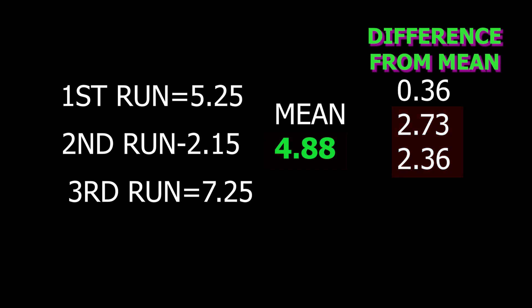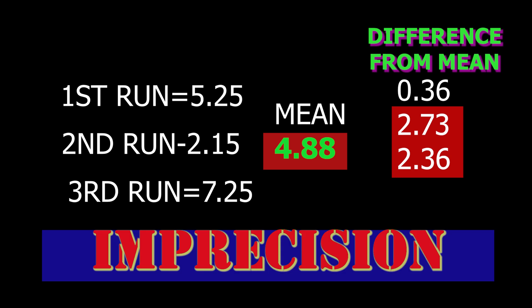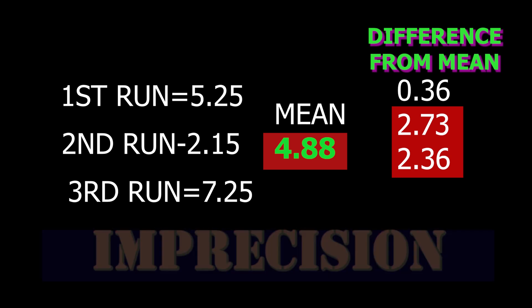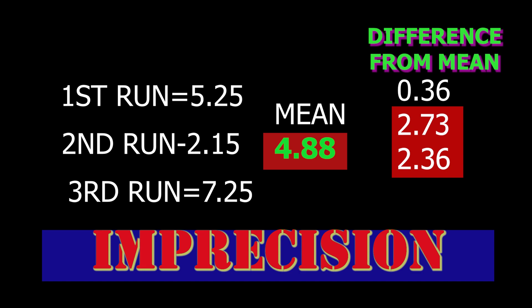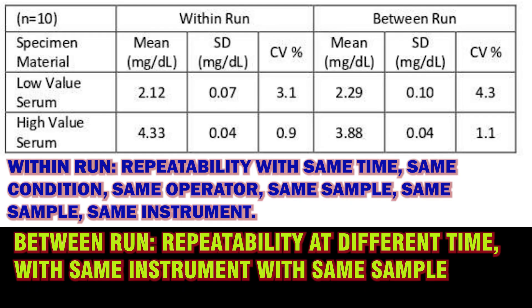If the instrument has very bad precision, the readings are far away from each other and the instrument cannot reproduce the same value, which indicates the instrument needs to be fixed before recalibrating the analyte. When we program the analyte calibration parameters, the instrument is programmed with a coefficient of variation percentage — the maximum percentage of variation allowed to pass calibration. If the values exceed that percentage, the calibration will automatically fail.